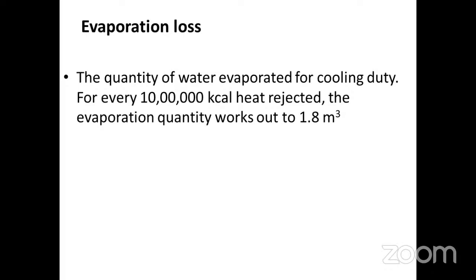Quantity of water evaporated for cooling duty. For every 1 million kilocalories, that means 10 lakhs kilocalorie of heat rejected, evaporation is in the range of 1.8 meter cube. It is a thumb rule. Actually, it has been calculated in various cycles. It is called evaporation loss. For every 10 lakh kilocalorie of heat rejected, the evaporation quantity works out to 1.8 meter cube.